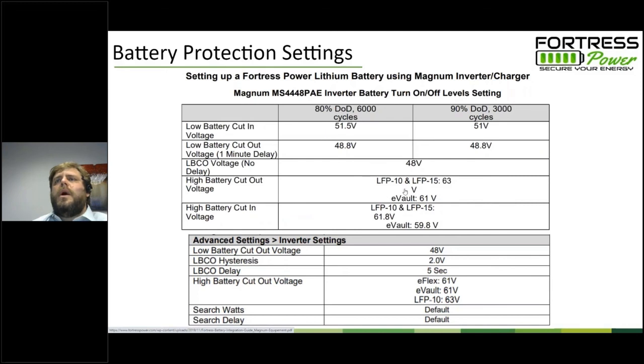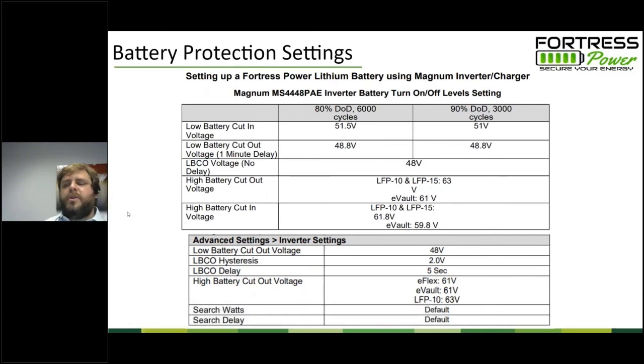Low battery cut in, low battery cut out. These are features that you program on the battery inverter, and then there are also features within our battery management system themselves. You can program the low battery cutout to turn the inverter off before our battery management system clicks in. The nice thing about a battery management system is if you mess up one of these settings, our battery is going to protect itself. A battery without a battery management system, you're relying on the inverter to be programmed correctly in order to protect the battery to its fullest.